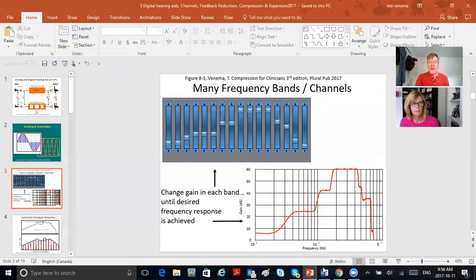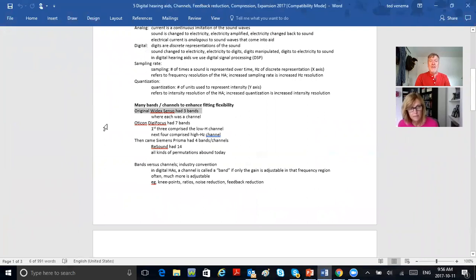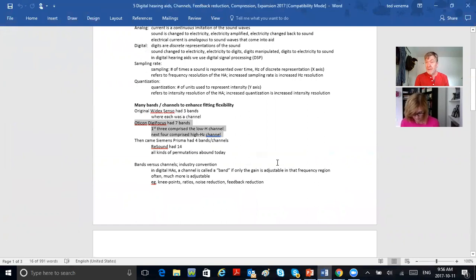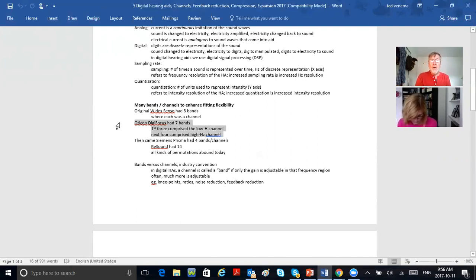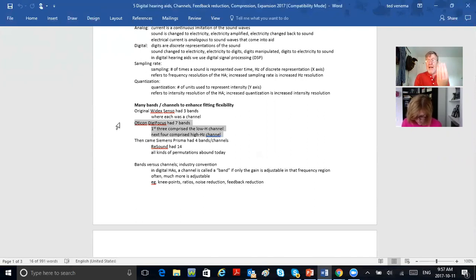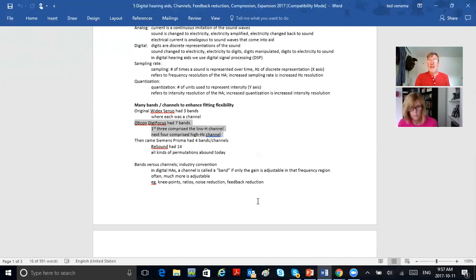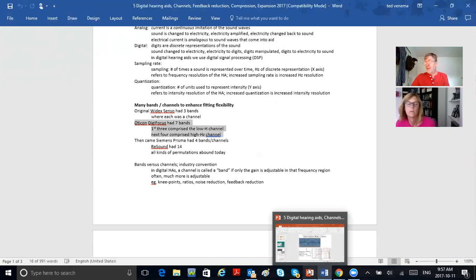The Oticon Digifocus was the second digital hearing aid in 1997. It had seven channels — more than the Widex Senso. They called them bands, where bands means frequency regions, and you can group bands into groups called channels.